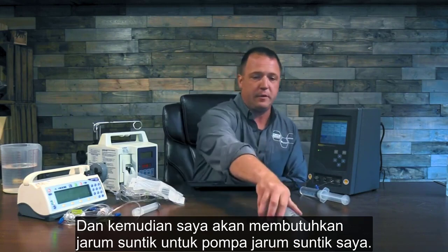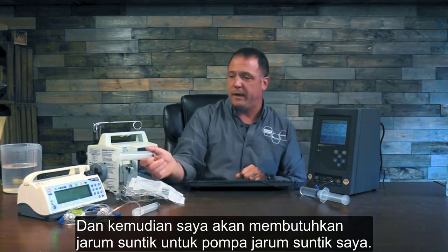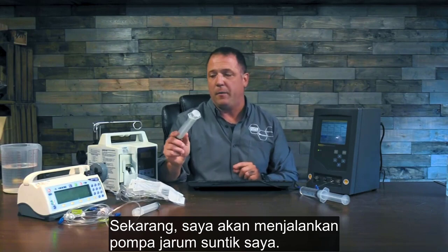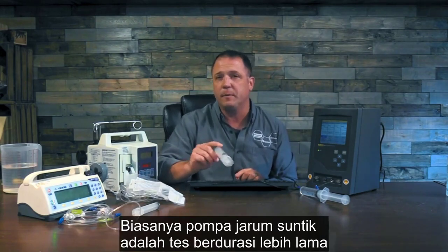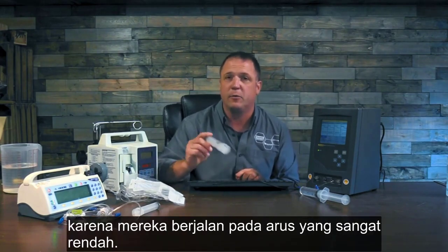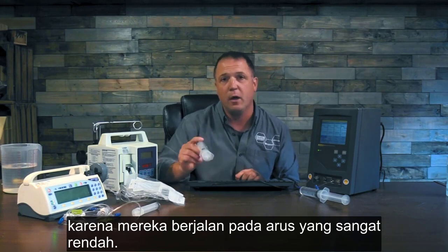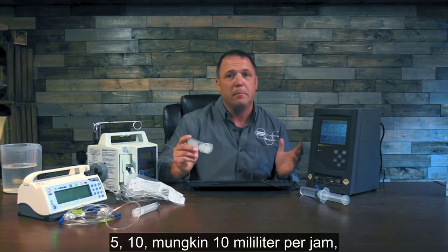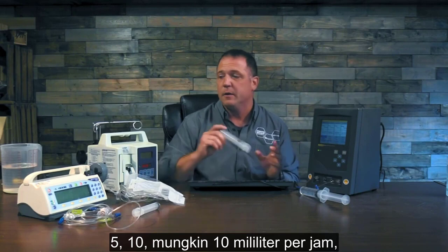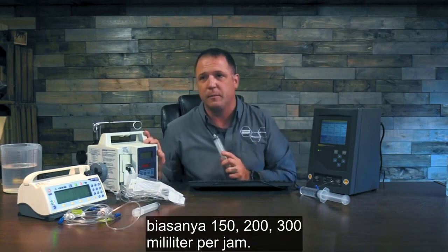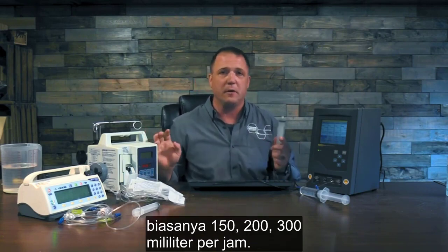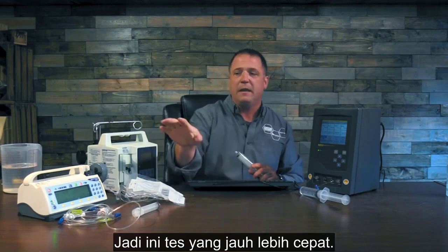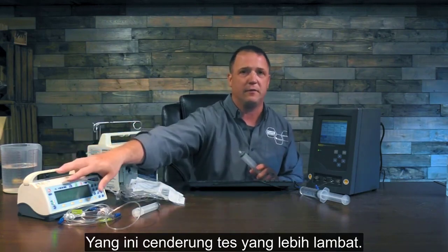And then I'm going to need a syringe for my syringe pump. Now I'm going to get my syringe pump started. Typically syringe pumps are longer duration tests because they're going at very low flows. You know, 5, 10, maybe 10 milliliters an hour. Versus infusion pumps where you're talking, you know, typically 150, 200, 300 milliliters an hour. So it's a much faster test. These ones tend to be slower tests.